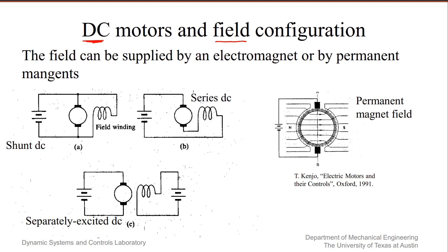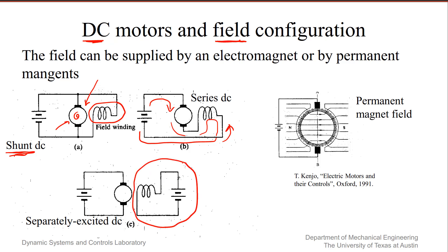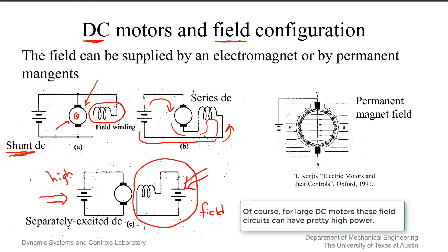DC motors are classified according to how the field is formed. I've shown here for reference a shunt DC motor — the term shunt meaning in parallel — so the field winding shown on the typical electrical schematic is in shunt or in parallel to the rotor windings. A series wound machine has the field formed by a series circuit. And then there's a separately excited DC motor that is formed by a completely different circuit, where you need to add power separately into the field coils from what you put into the armature, which you can think of as the high power transmission.